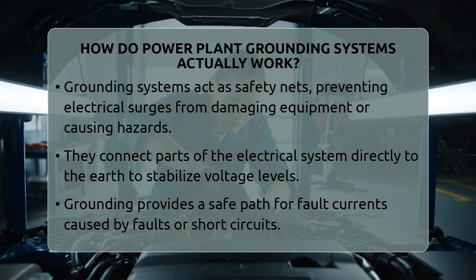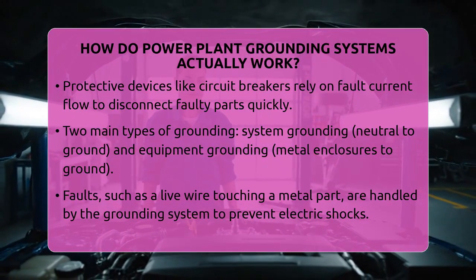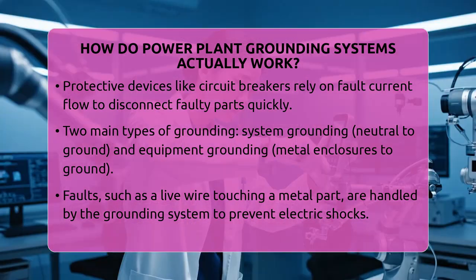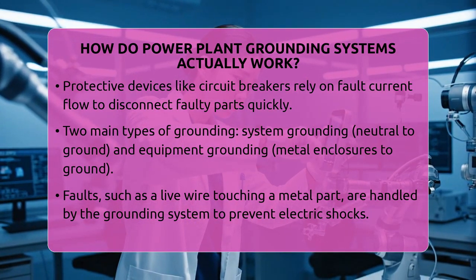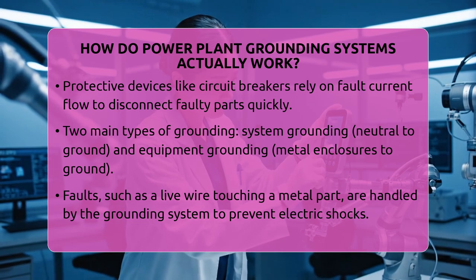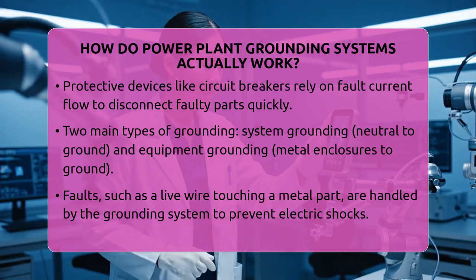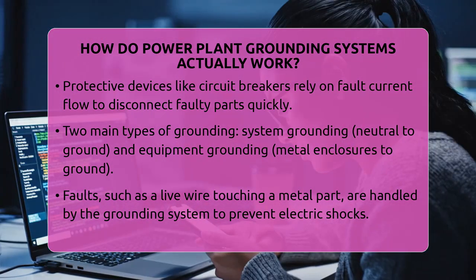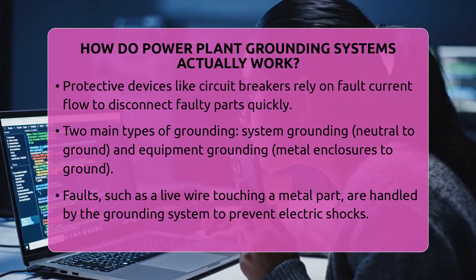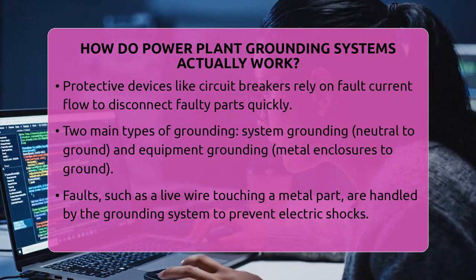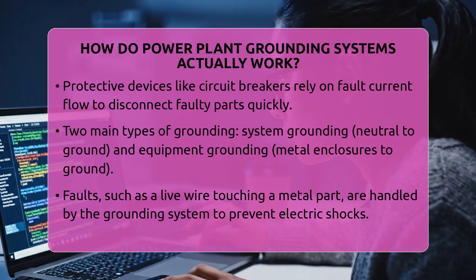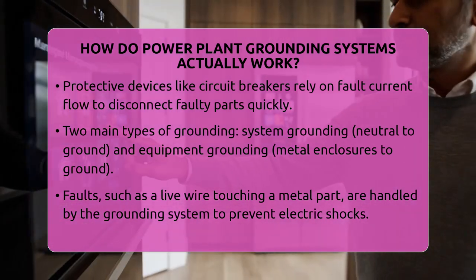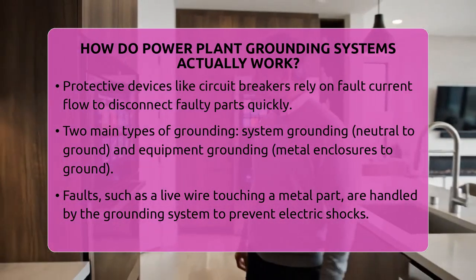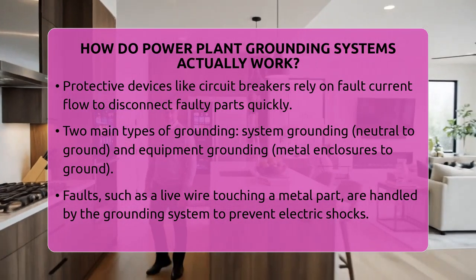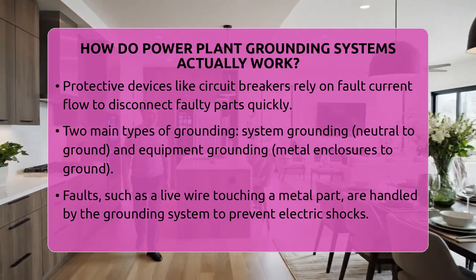preventing fires. There are two main types of grounding in power plants. System grounding connects the neutral point of the transformer or generator directly to the ground. This sets a reference point for the entire system and makes fault detection easier. Equipment grounding, on the other hand, links metal enclosures and non-current carrying parts of electrical equipment to the ground. This prevents these parts from becoming energized and causing electric shocks.